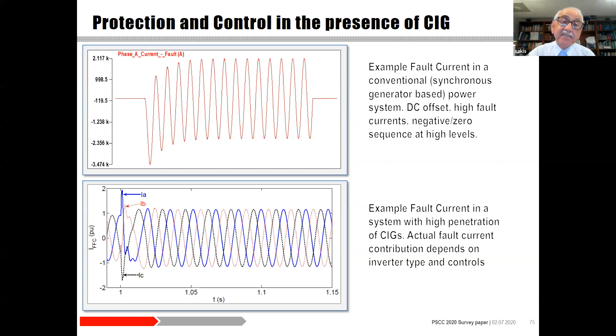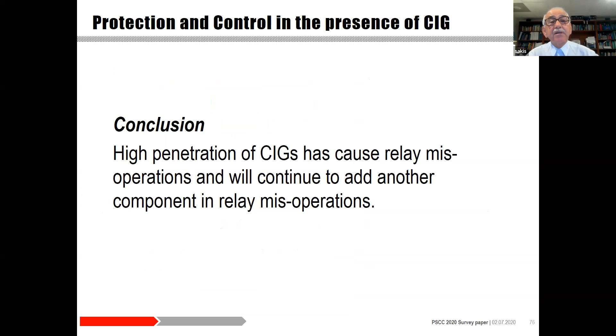The lower set of traces is the current following a fault in a system that has inverter interface generation. And you see that the fault currents are relatively small, and if we analyze these waveforms, we do not have negative and zero sequence components, which affects the operation of the system. So these different characteristics cause problems. And the conclusion is that as we have more and more converter interface generation, we're going to have more and more problems with protection and control in the power system.